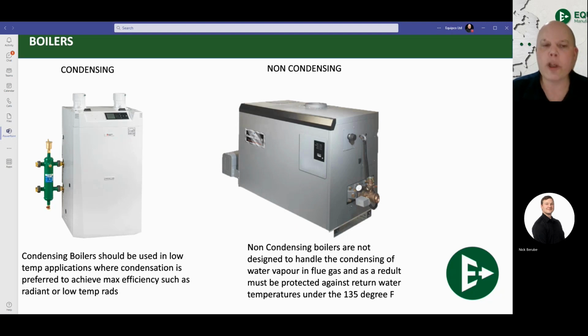So how do you make it condense in the first place? You make it condense by condensing the flue gases. You do this by bringing back cool water temperature, anything beneath the 135 degrees Fahrenheit mark. That's how you make these boilers condense. The more condensate you create, the more BTUs are added to the heat output of the system, the higher the efficiency of these boilers gets. The burner itself is only about 89 to 90%. The 90 plus all comes from condensation. If you don't make the boilers condense, you are not going to have that high 95, 96, 97% output.